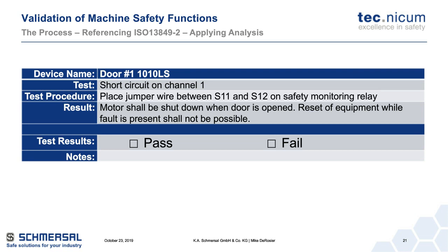Pass or fail. You're not developing a validation plan for things that you do not detect. You address that kind of thing in your analysis phase to say, hey, we have fault exclusions, we're not detecting this, and this is why. You have it properly documented. But wherever you can detect something, that's what you want to test for.